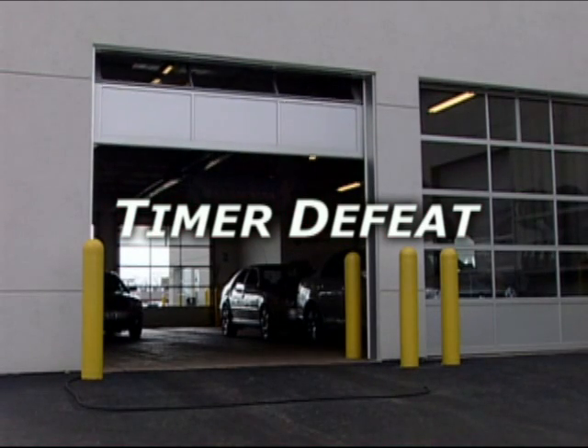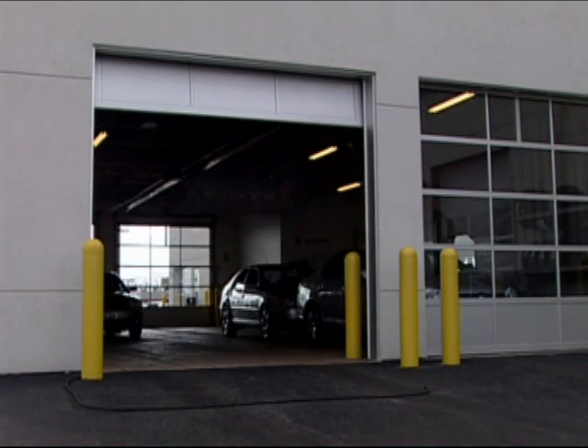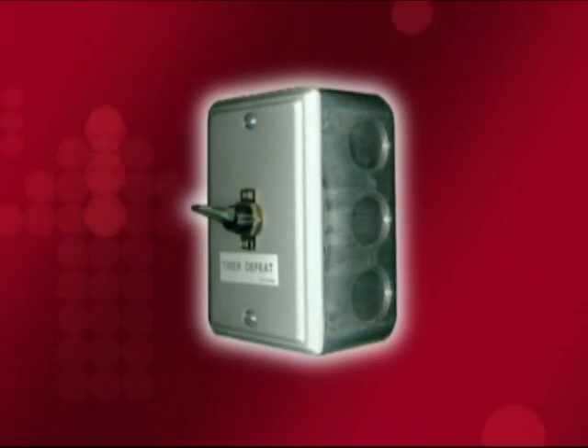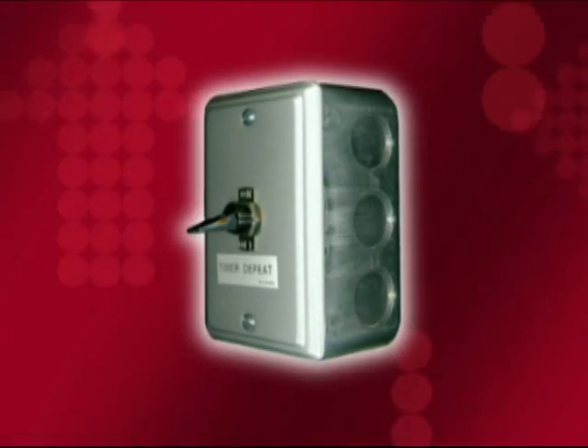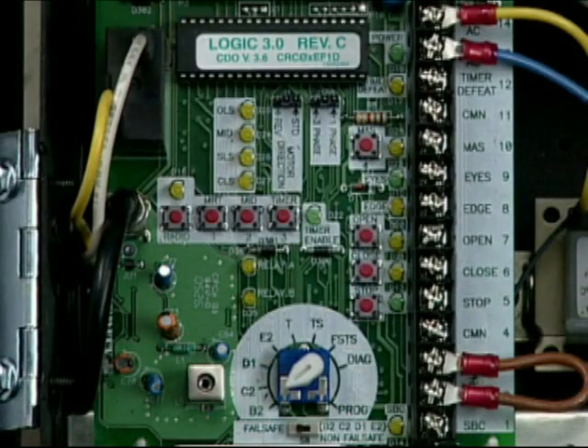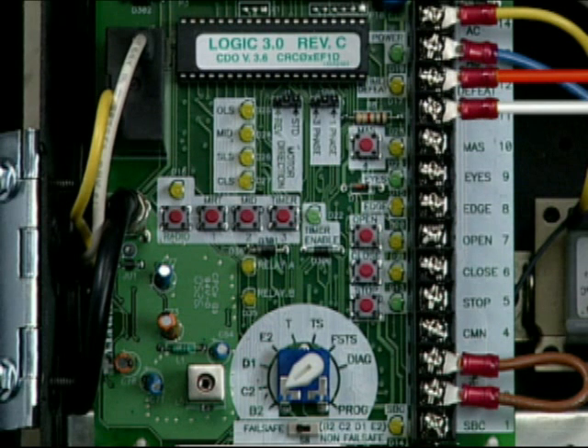The timer defeat feature on the Logic 3.0 control board allows a door to be left open without timing out to close. This feature requires an optional timer defeat switch accessory. To use this feature, you need to connect the timer defeat wire to the timer defeat input and the common wire to the common input on the low voltage terminal strip. The automatic close timer is disabled when the timer defeat switch is switched on. The timer defeat LED on the logic board will turn on when the automatic close timer is disabled.